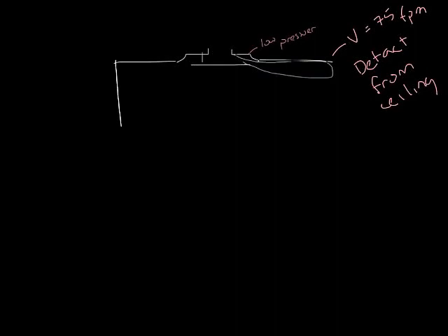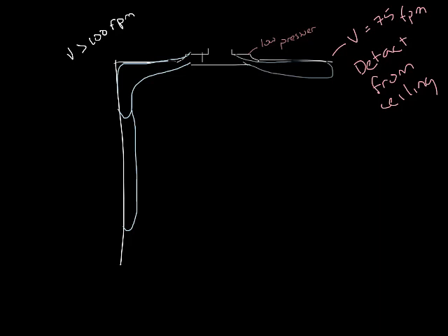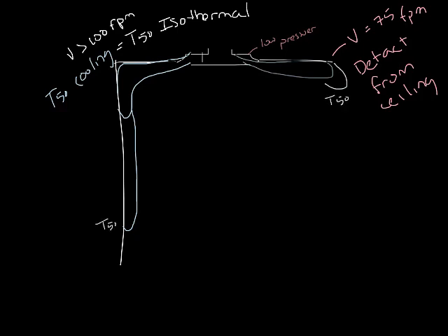So let's say the diffuser is close to a wall. The air pattern is going to go down the wall. If it hits the wall at greater than 100 feet per minute, this will affect the throw so that the cooling T50, the 50 foot per minute cooling throw, will be the same as the cataloged isothermal T50. If it hits the wall at a slower velocity, it will still have the shortened throw like the other side of this drawing.